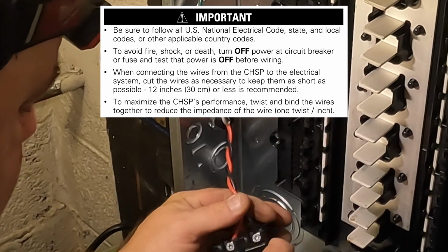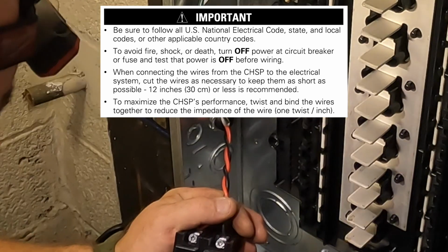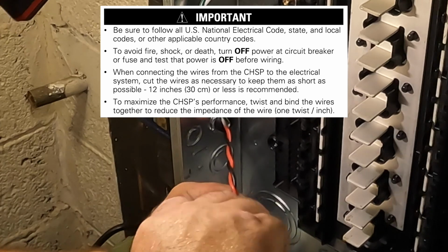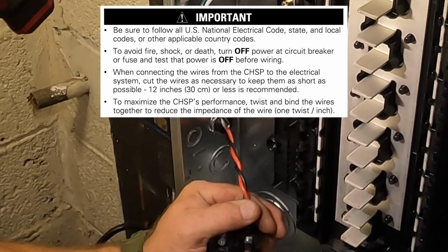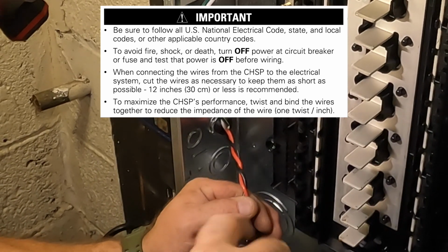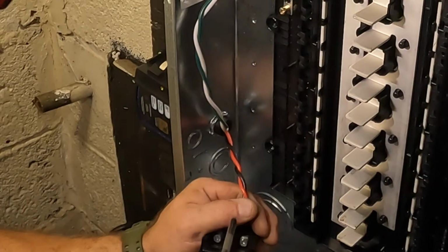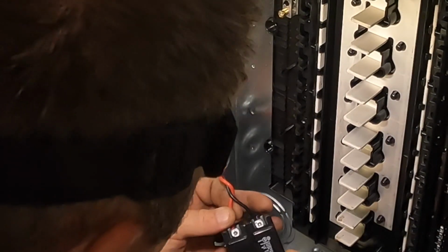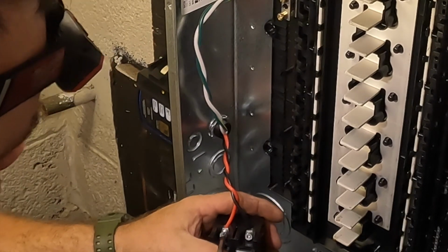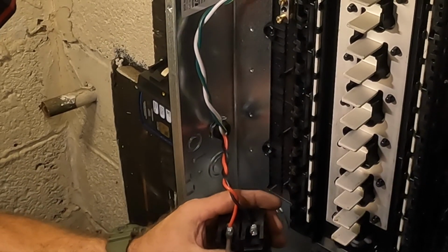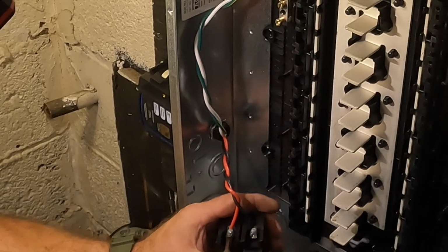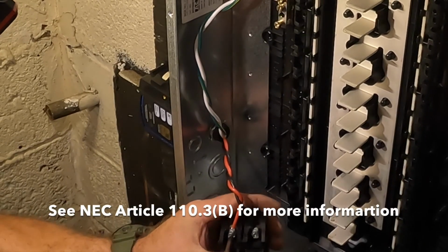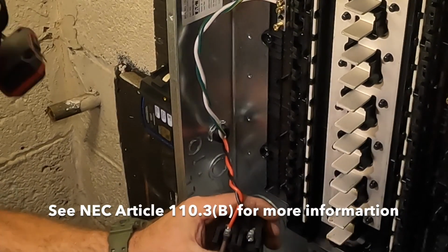To maximize the Cutler-Hammer surge protection device performance, twist and bind the wires together to reduce the impedance of the wire, 1 twist per inch. I just wanted to highlight these important instructions by the manufacturer because, of course, the National Electrical Code also has a section that demands or requires that we install to the manufacturer specifications.